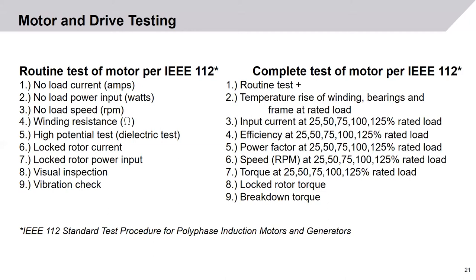The complete test also measures current efficiency, power factor, speed, and torque at 25, 50, 75, 100, and 125% of rated motor load. On top of all those values, they will still check lock rotor torque and breakdown torque.